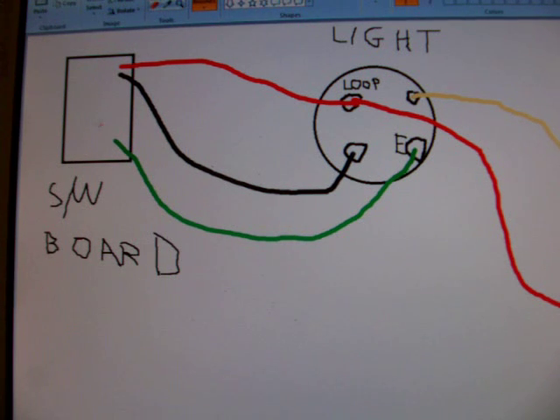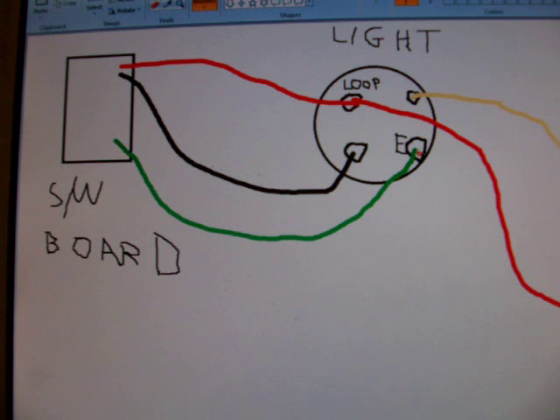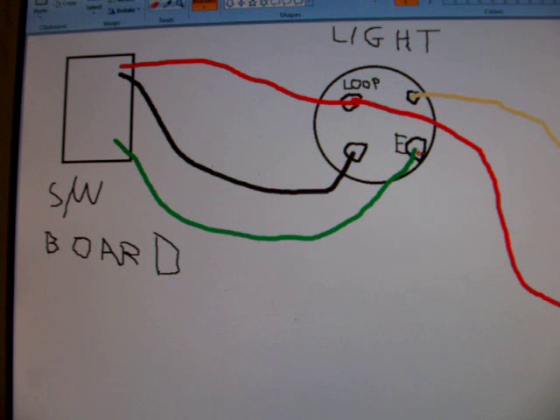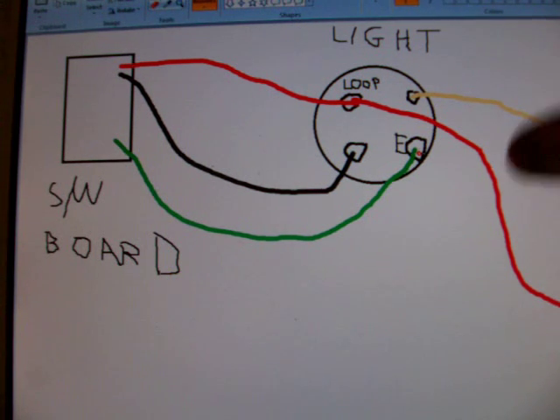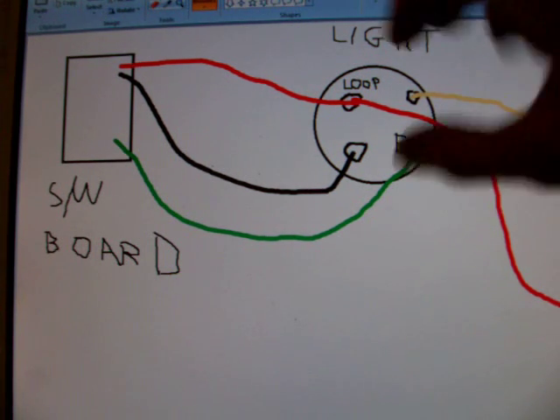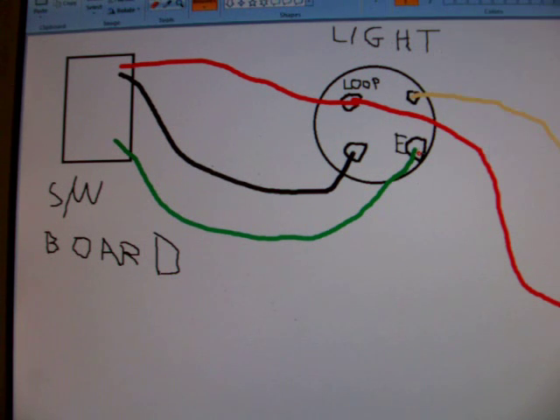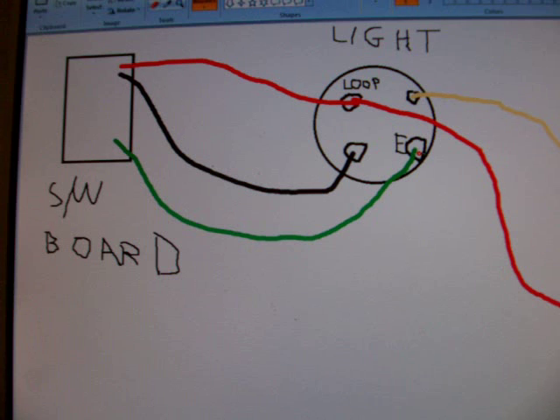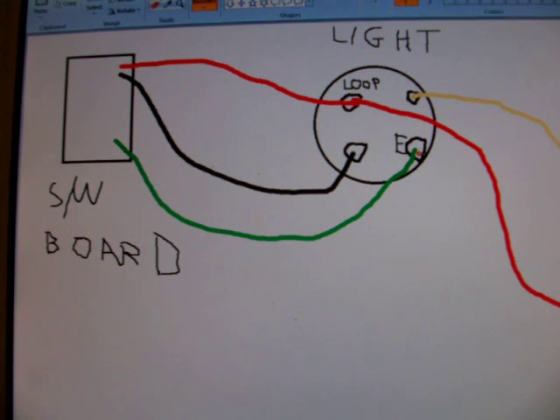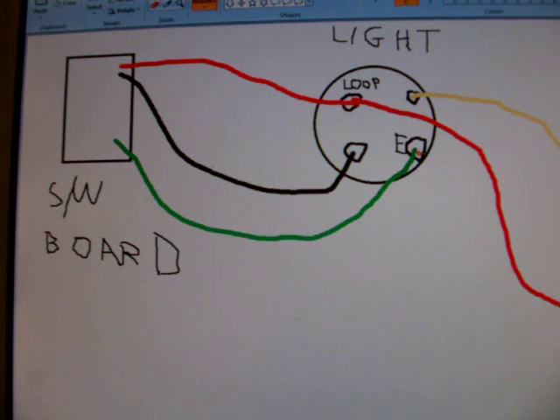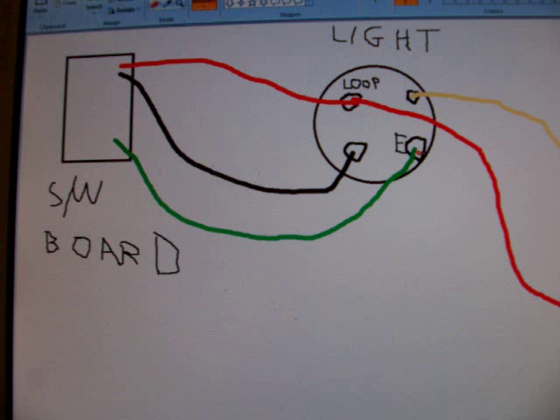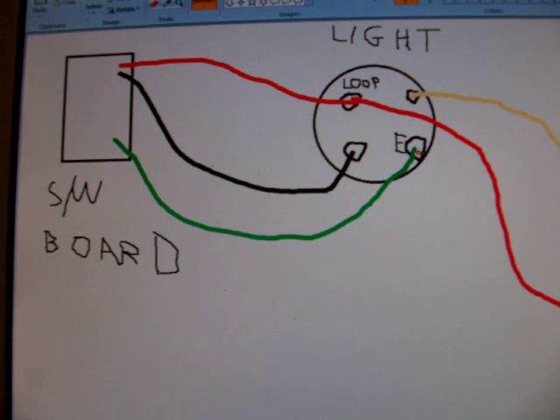So anyway, your earth wire just goes to the earth terminal on the fixture. Now, when you put in multiple light fixtures, such as we have one, two, three in this room, you just simply jump the wires, the three conductors to the next fixture along. So it makes wiring up very, very quick and very straightforward. It also means there's a lot less stuffing around at the switch end.